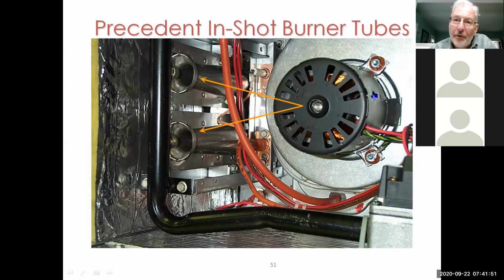The one thing you'll notice is on these units, even if it's a single stage rooftop, we'll use a two-stage inducer. We just don't energize low speed. And that's the same on our 80% furnaces now. You'll see that these have two-stage inducers on them, but we don't always use the low stage. It's just for parts availability, it makes it a little easier. But this is our spark ignition right here. This is our flame sensor right here.